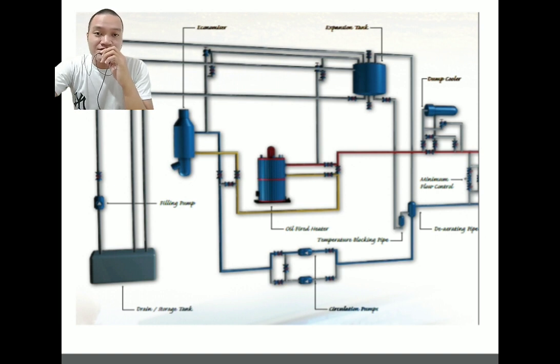Third is once the temperature has dropped to 200 °F or 93 °C, the residual heat has been removed and you are now safe to shut off the pump.